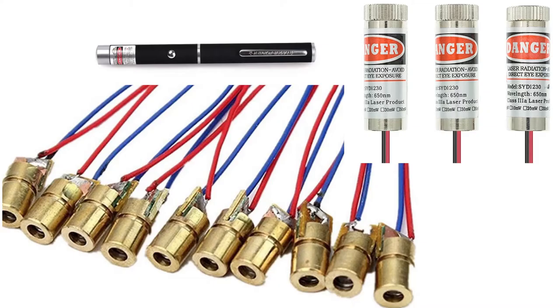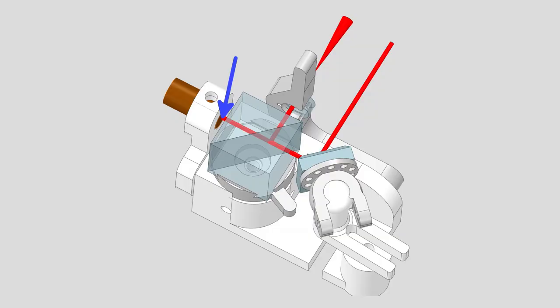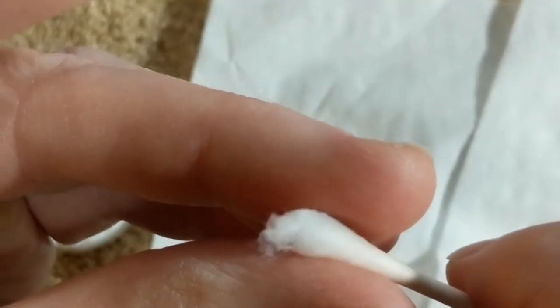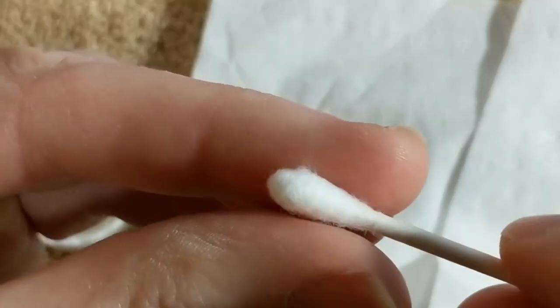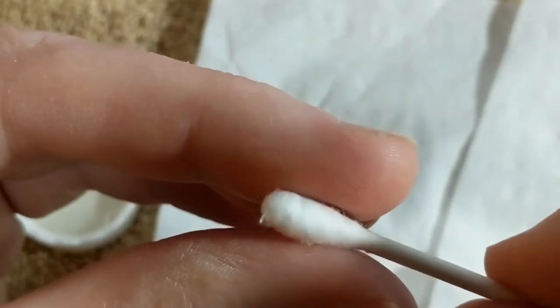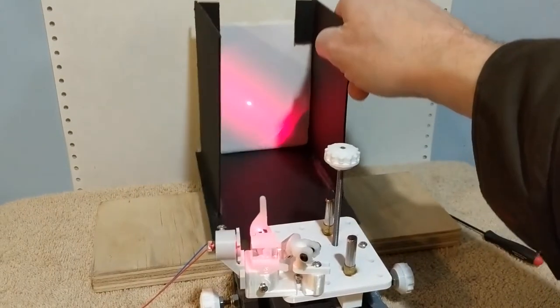The semiconductor laser will not have any issues, but the collimating lens in the laser can be a problem along with the splitter, the flat, and the diverger. And actually even the surface of your mirror, possibly. It took me dozens of cleanings before I realized I was often cleaning the wrong optic.